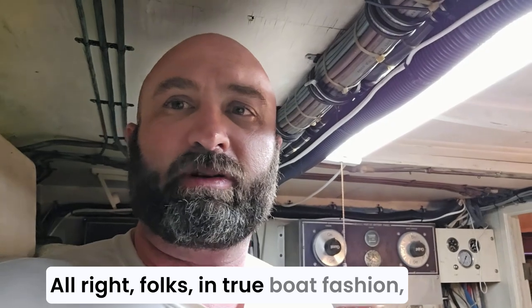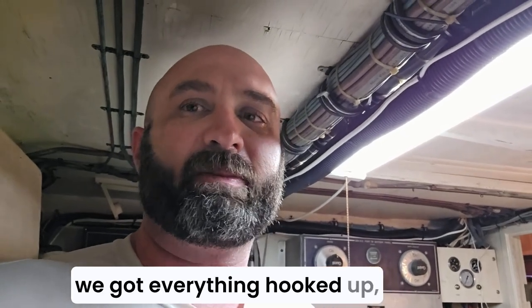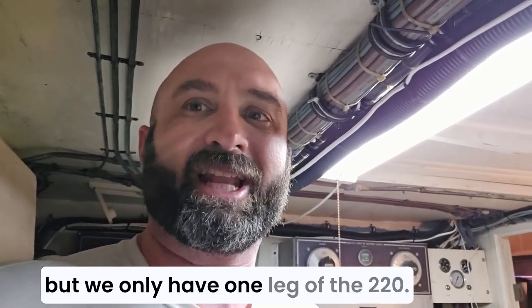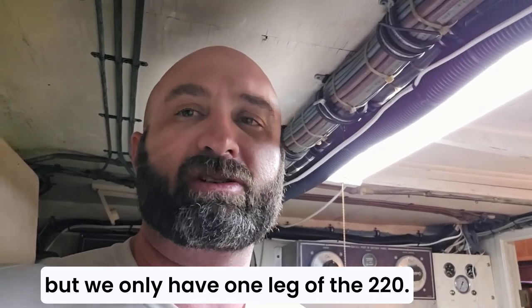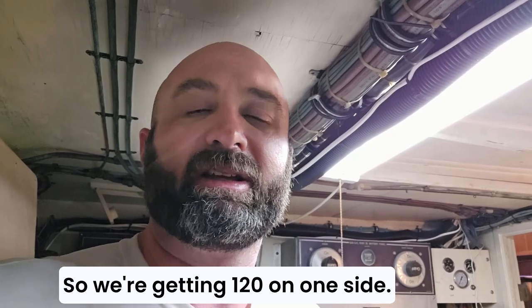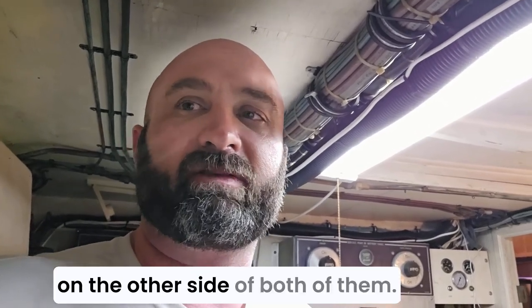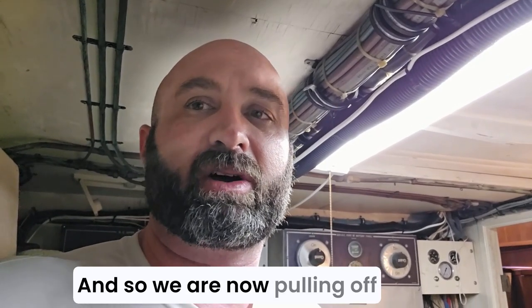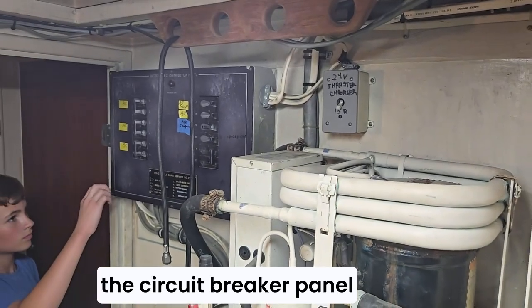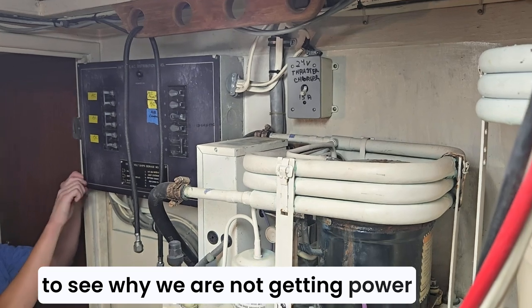In true boat fashion, we got everything hooked up, but we only have one leg of the 220, so we're getting 120 on one side. We should be getting 120 on the other side of both, so we are now pulling off the circuit breaker panel to see why we are not getting power from that panel to this box.